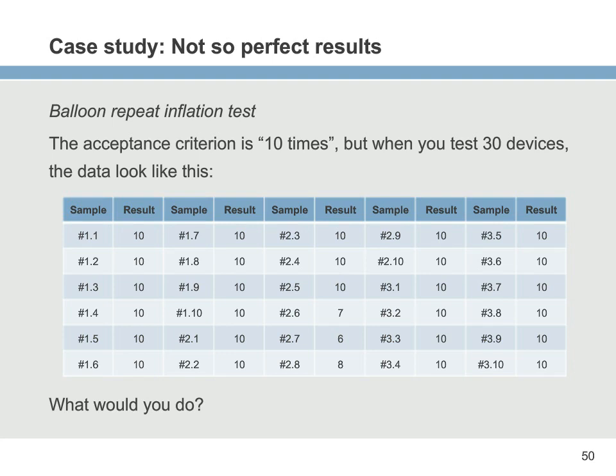So I said, I think that's a perfectly relevant justification. We didn't do a lot of sample size and statistical justification, things like that. Guys, I think that 6 is probably a fine number for an acceptance criteria. That's what your worst balloon is at. I think that's fine because that's double 3, and 3 has only occurred once in 6 physicians ever in their career. So I think that's acceptable. And that's exactly how we wrote it.